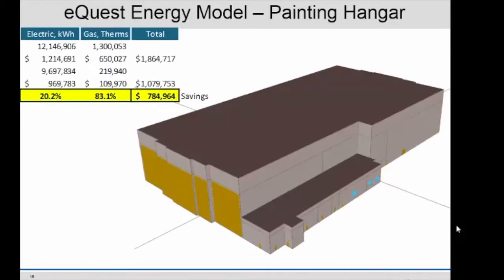And this is a model. We do eQuest models because we want to model. This is ESPC. This is Energy Savings Performance Contracting. The ESCO is responsible for the energy savings. We've got to make sure we calculate the savings properly. So we use a model, a 3D model. This particular corrosion control hangar, painting hangar, almost $1 million a year in savings in just one building. It's a big number.